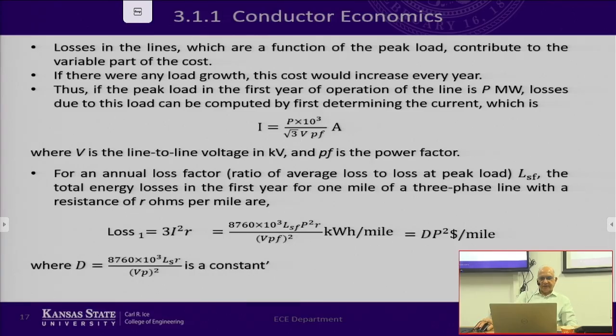Let's assume the peak load in the first year of operation of the line is P megawatts. We are given that we have to select conductors for a load of P megawatts in the first year. So we ask, how many losses will there be? First we calculate I: P is in megawatts, multiplied by 10 to the power 3. Voltage is in kilovolts, so this factor of 10 to the power 3 has to be included, because P is 10 to the power 6, and this is 10 to the power 3, so those cancel and you're left with 10 to the power 3. Then square root of 3 times V, the line-to-line voltage, times the power factor, gives you the current.